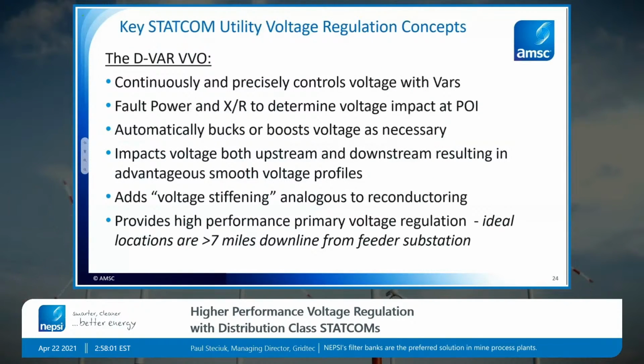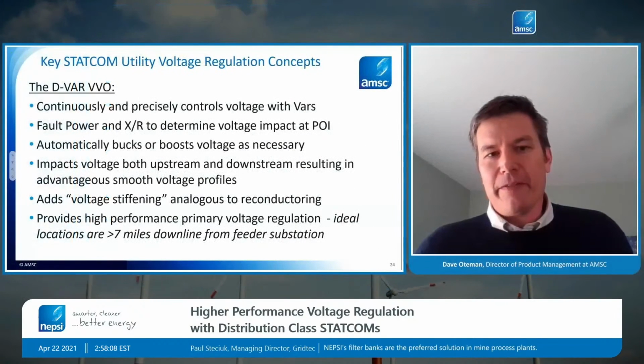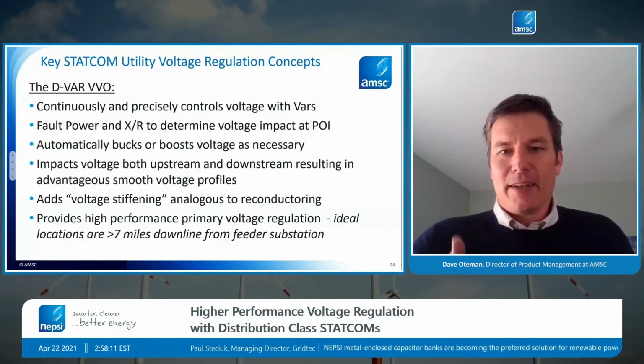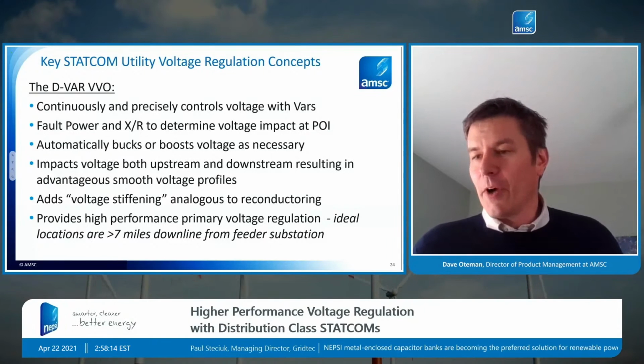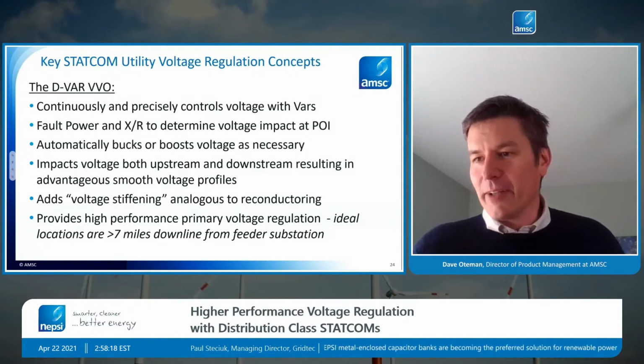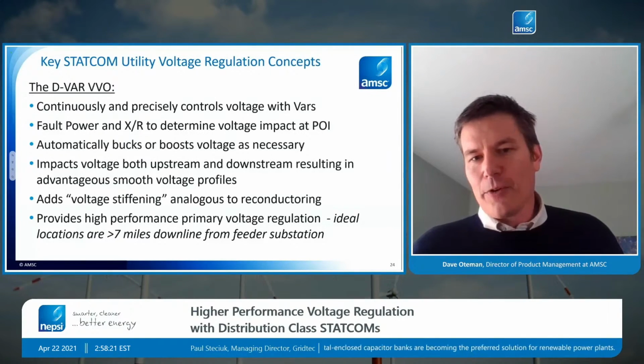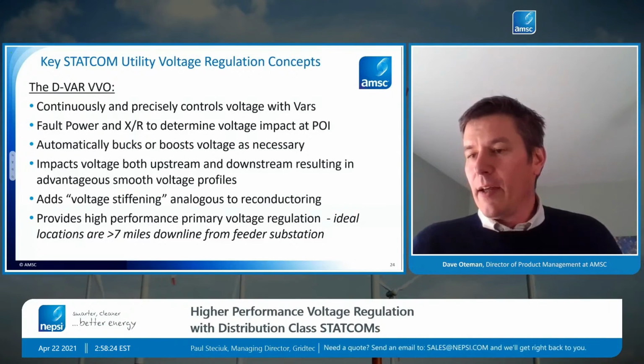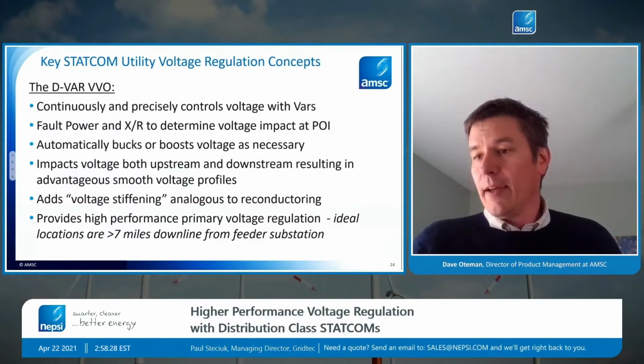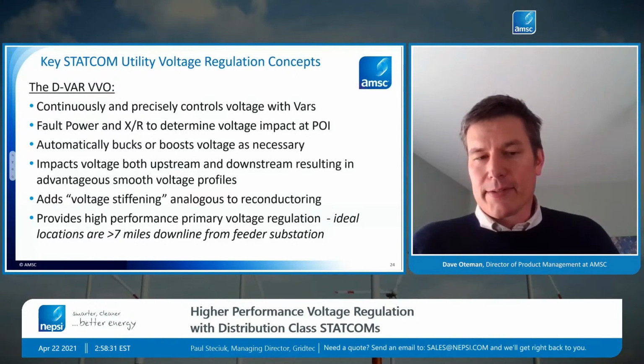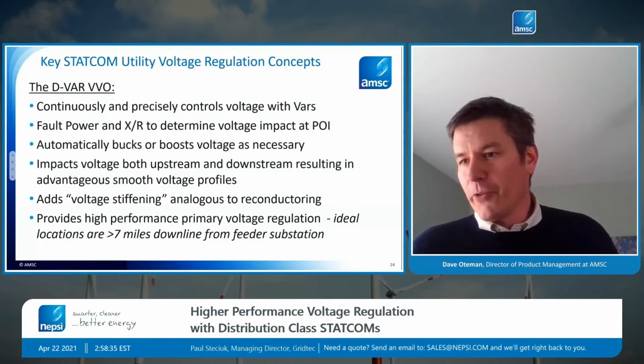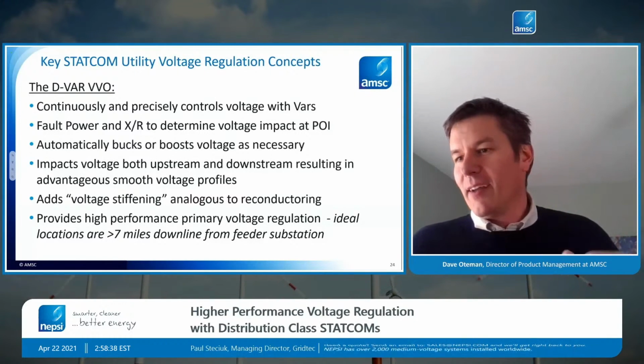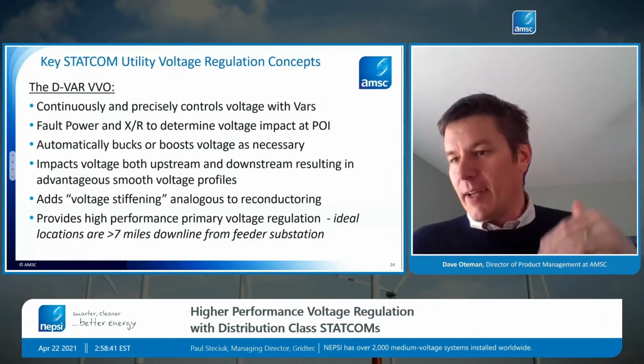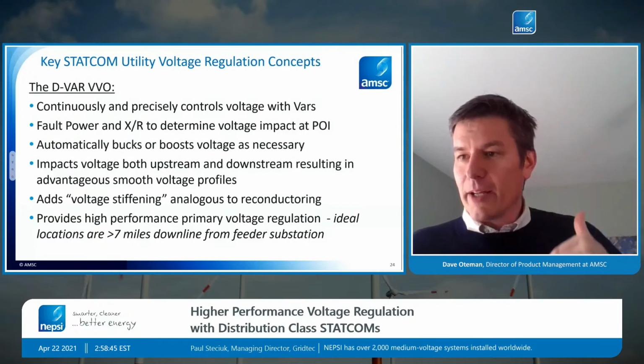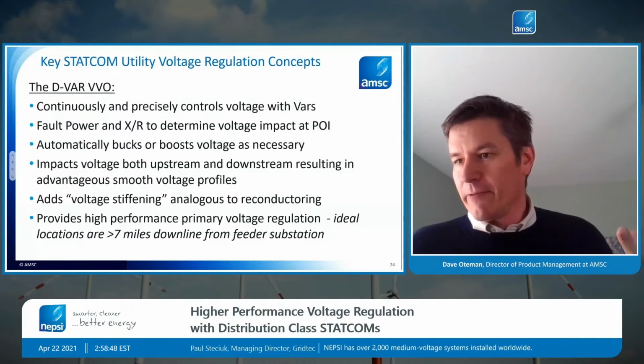So to recap, the principle of operation for voltage regulation on a distribution system, what we just reviewed. So the D-VAR VVO, number one, continuously and precisely controls the voltage using VARs. So shunt device, not a series device, using VARs to regulate that voltage. You need fault power and X over R, and that's all you need to be able to determine how much impact the VVO will have, depending on where it's installed in the system. The VVO automatically bucks or boosts voltage as necessary, so that's one control mode. It doesn't have to be told to buck or told to boost separately. It just needs a voltage set point, and it's going to automatically do the right thing on the feeder, also regardless of power flow direction.